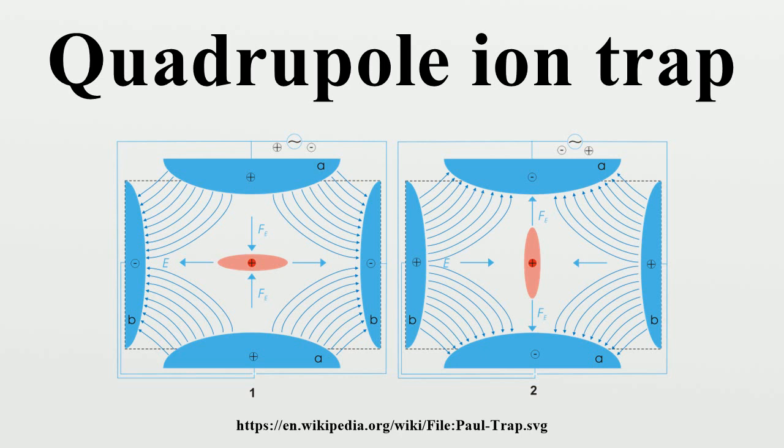The Paul trap is designed to create a saddle-shaped field to trap a charged ion, but with a quadrupole, this saddle-shaped electric field cannot be rotated about an ion in the center. It can only flip the field up and down. For this reason, the motions of a single ion in the trap are described by Mathieu equations, which can only be solved numerically by computer simulations.